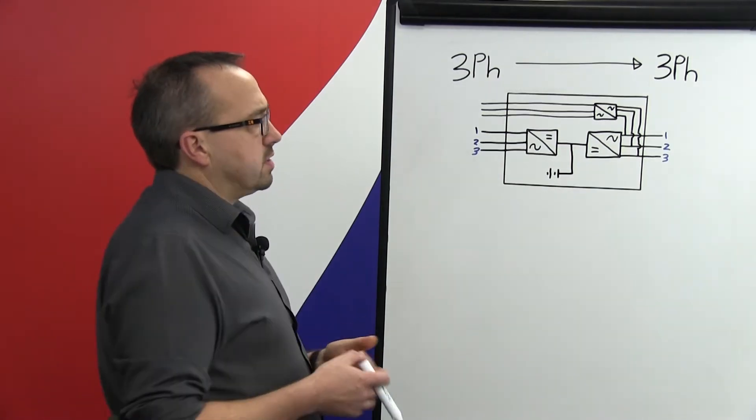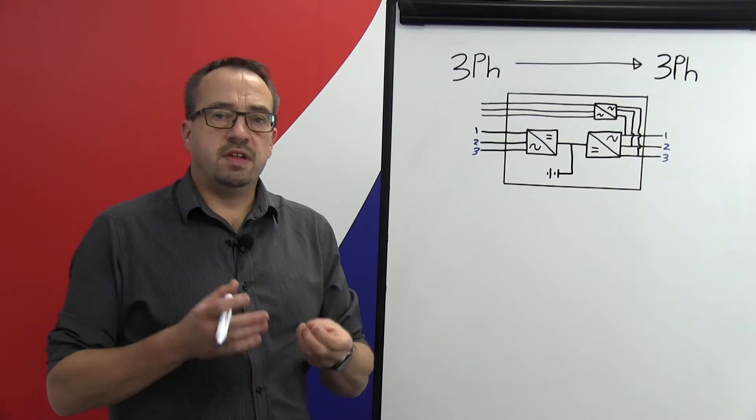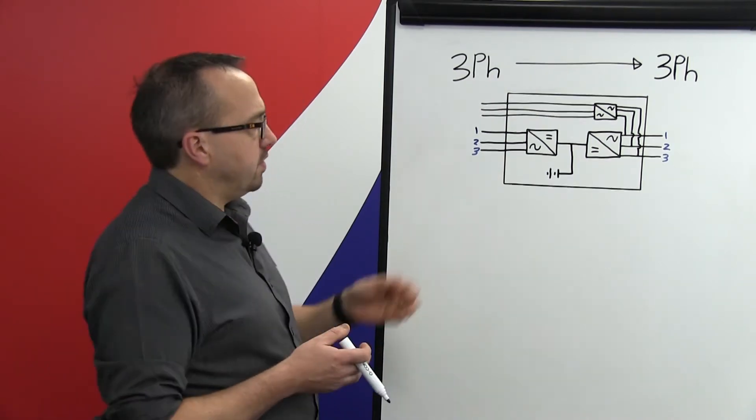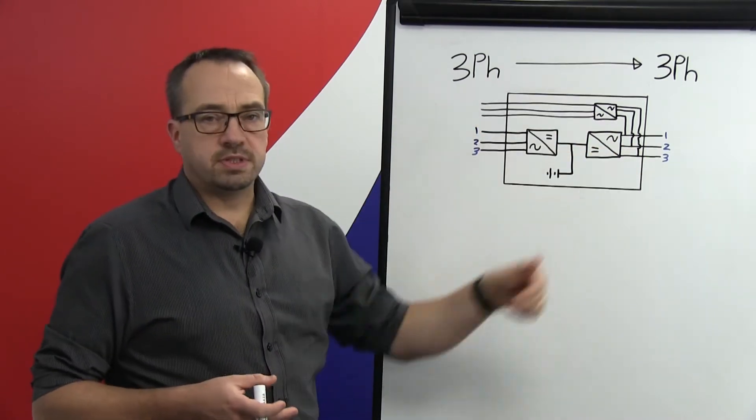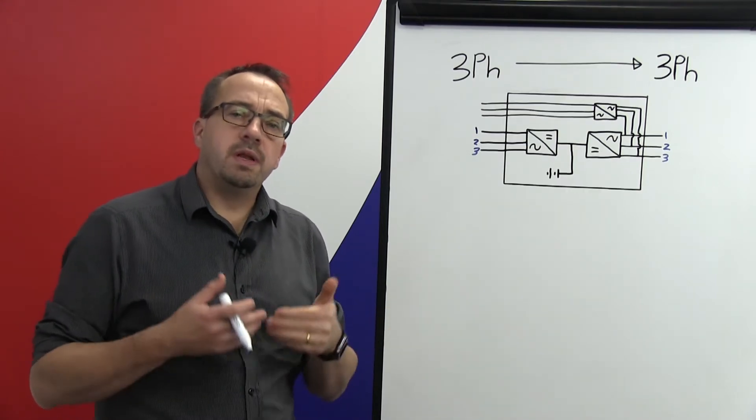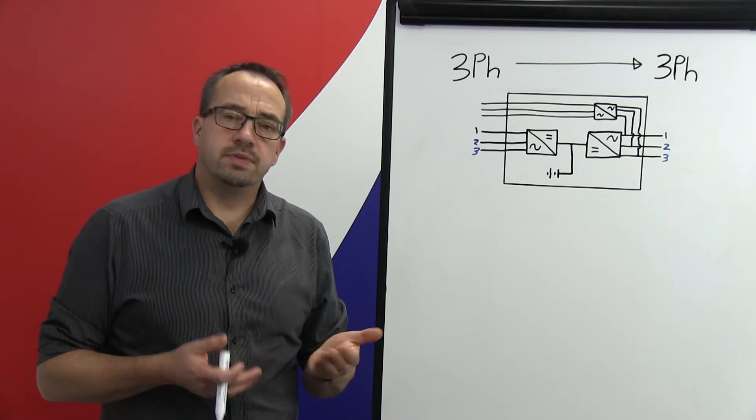Now one of the main benefits of the online dual conversion UPS system is the AC to DC, DC to AC conversion. Because we make this conversion anything that is passing into the UPS system is never replicated on the output side of the UPS system and therefore both the input and the output remain completely independent of one another and this is referred to as VFI voltage and frequency independent.